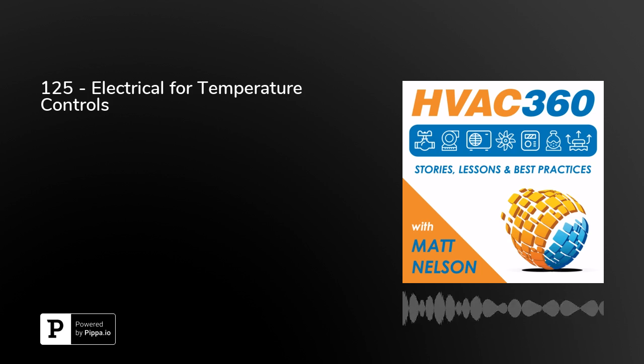So, what are we dealing with here? What we have are line voltage controls. Those are typically, and we've talked about those before, for standalone, simpler control devices. And these are more prevalent in a place that lacks a building automation system. But that's not what we're talking about here. So those are line voltage controls. We're talking about low voltage controls. And typically that's going to be 24 volts.